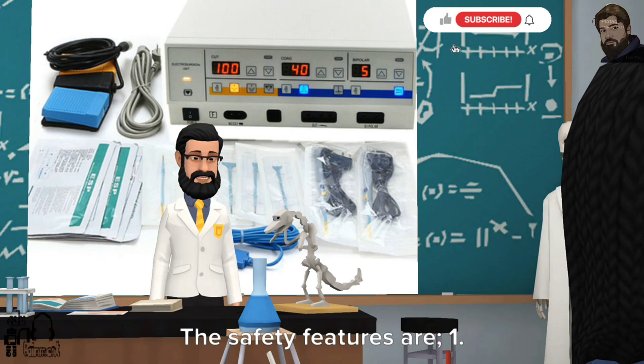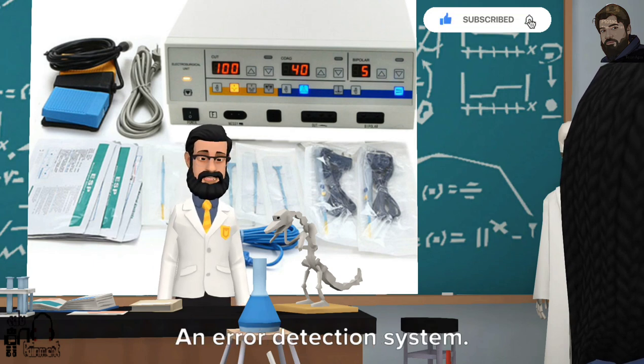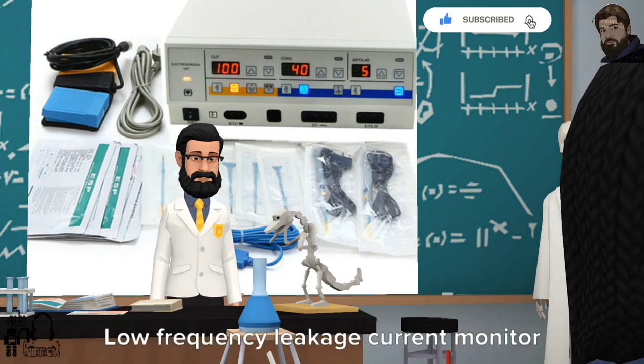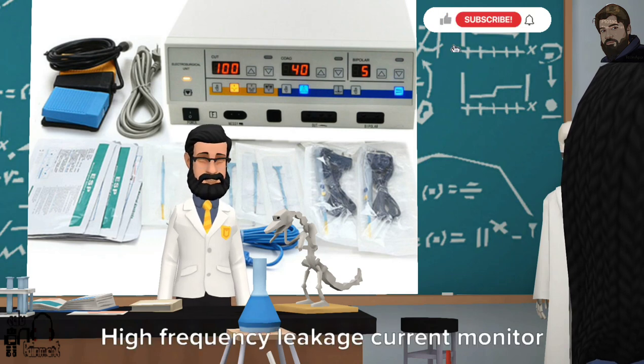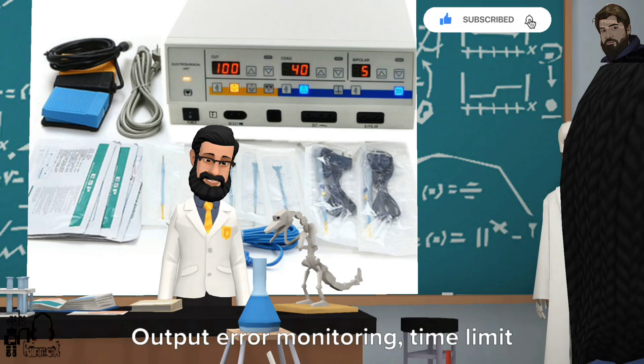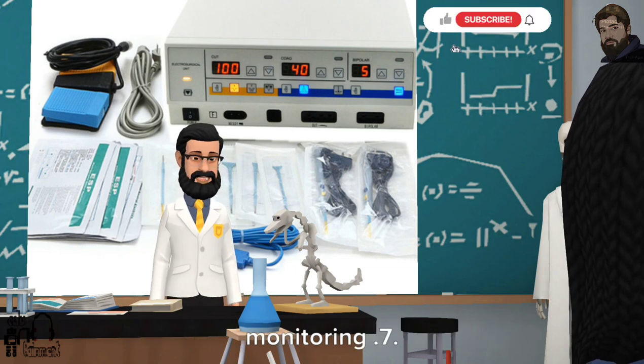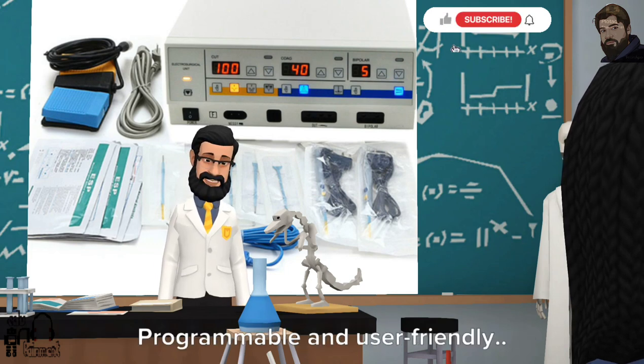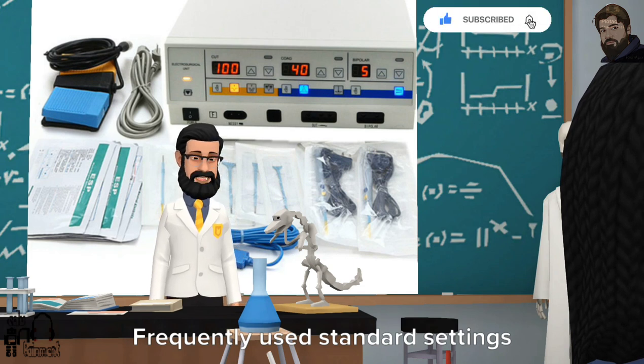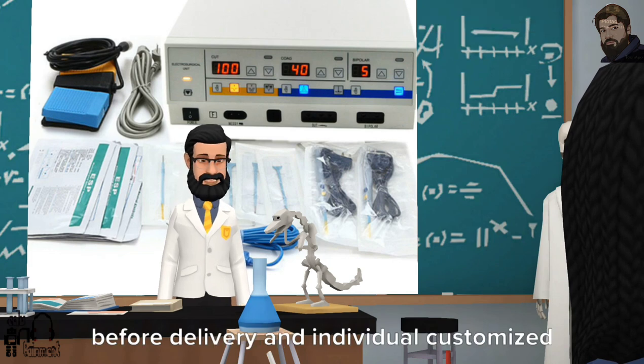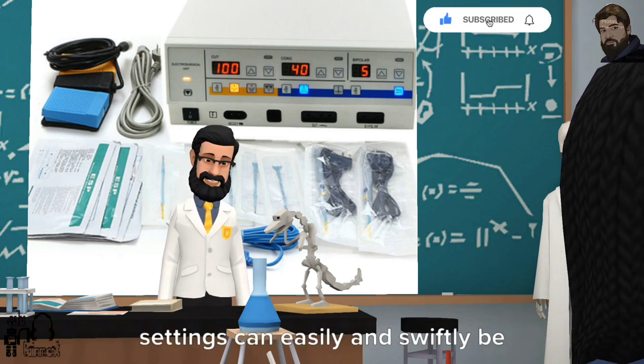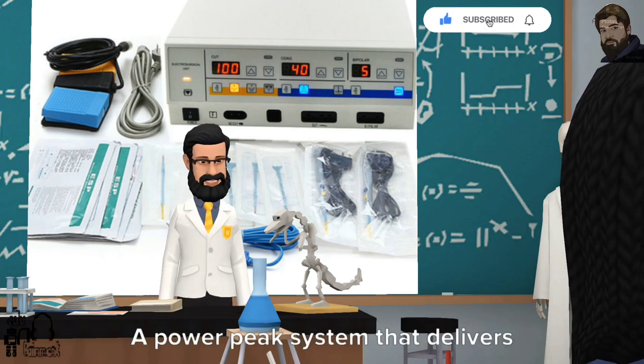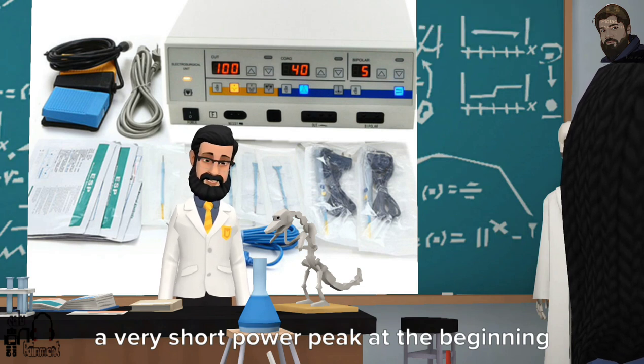What are the safety features? The safety features are: 1. An error detection system, 2. An error signaling system, 3. An error storage system, 4. Low frequency leakage current monitor, 5. High frequency leakage current monitor, 6. Output error monitoring and time limit monitoring, 7. Operating errors and neutral electrode safety system, 8. Programmable and user friendly, 9. Frequently used standard settings can be programmed by the manufacturer before delivery and individual customized settings can easily and swiftly be programmed later.